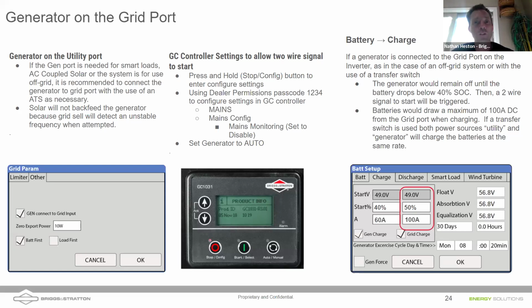So if you've got a smaller generator, we recommend prioritizing load first, and then any additional extra power that the generator can put out below the limit that you set, right? So if you set an overall limit of 10 kilowatts of power and 5 kilowatts is being used for load, it'll use that remaining 5 kilowatts for battery charging. Okay, so if you're running a small generator, like a portable or a smaller unit that can barely back up the whole home, prioritize load first.